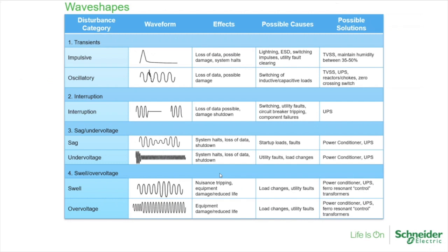If you're seeing oscillatory transients all the time, it could be a cap bank that's operating more often than it should. Then you try to understand why it is operating so often. Is it the customer's load? Are they bringing on something that's constantly causing the power factor to drop a lot and having to switch on? I haven't usually seen cap bank transients with as large a peak as, say, a lightning strike. But if they are exceeding your voltage ratings, that is ultimately causing damage to your equipment, especially if it's frequent and over time.